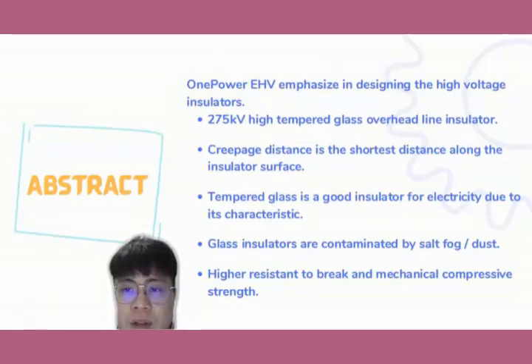In short, the glass insulator has higher resistance to breaking as compared to ceramics, and its mechanical compressive strength is higher. Generally, glass is a good insulator for electricity due to its characteristics. So high voltage insulators are made from glass, porcelain, or composite polymer materials. Nowadays, glass insulator has become one of the most popular insulators that are widely used in power transmission and distribution systems in numerous countries. This is due to the reason that glass acts as a good insulator since the electrons are tightly bound to each other. Hence, the electrons are not free to move around. This characteristic has disabled glass to conduct electricity.